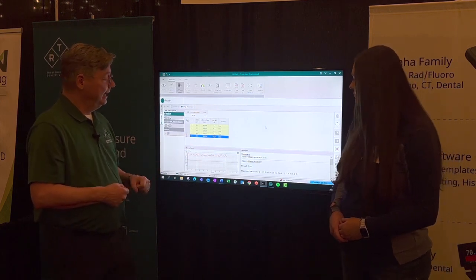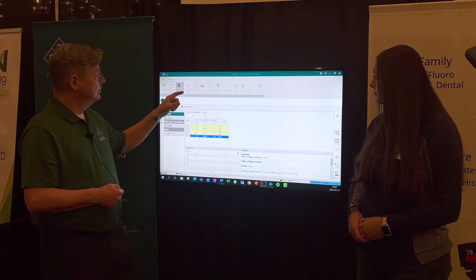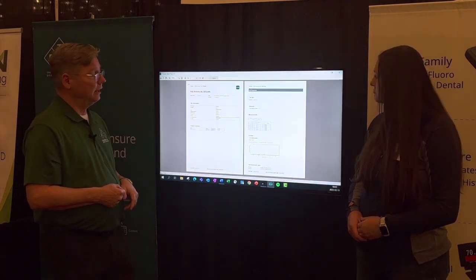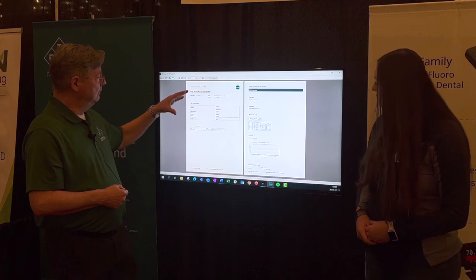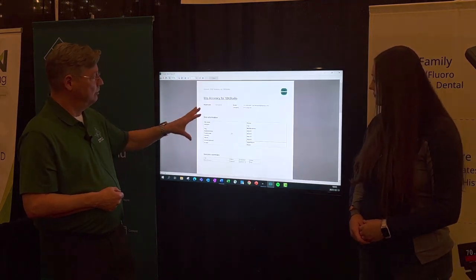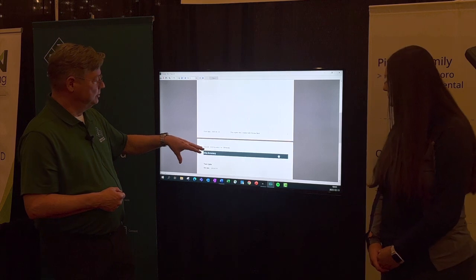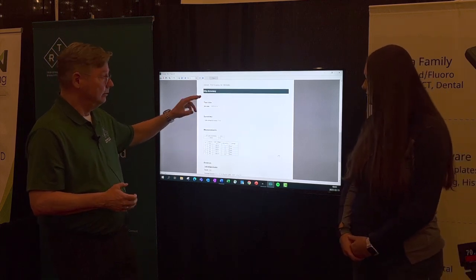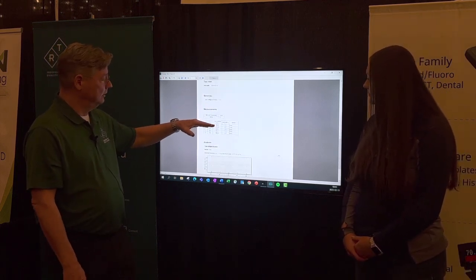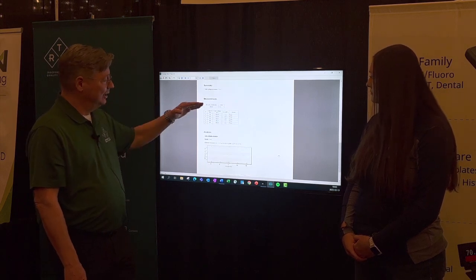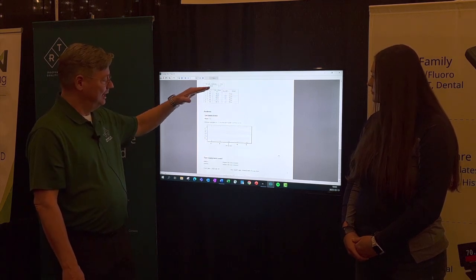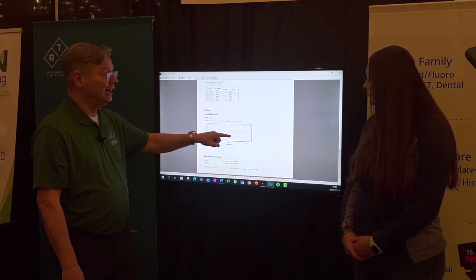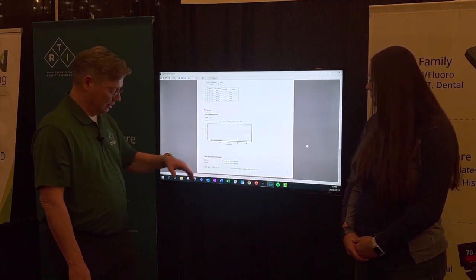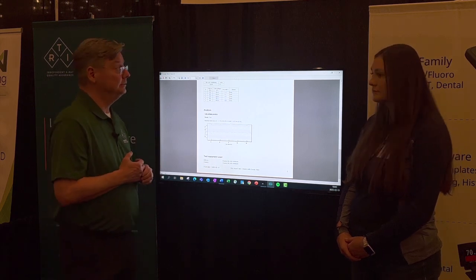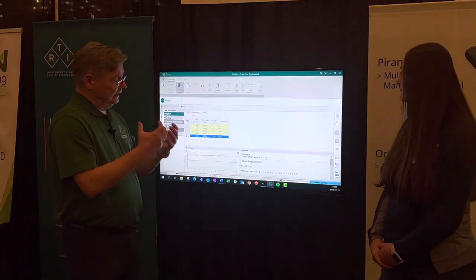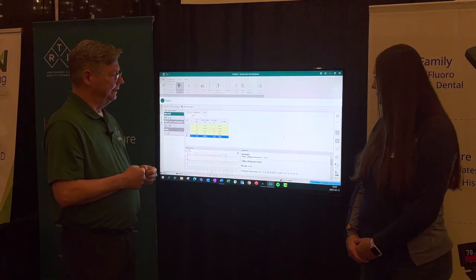And immediately after the last exposure, there is a report generated as well. A report which will give us the possibility to add site information where we performed this test. Also, when it was done, what date it was done, what was the result of it, the summary, pass or fail. And here are the measurements and all the documentation regarding that, a plot of how the measurements ended up, and the serial number of the instrument being used for that. So it collects and gets that report done quite fast.